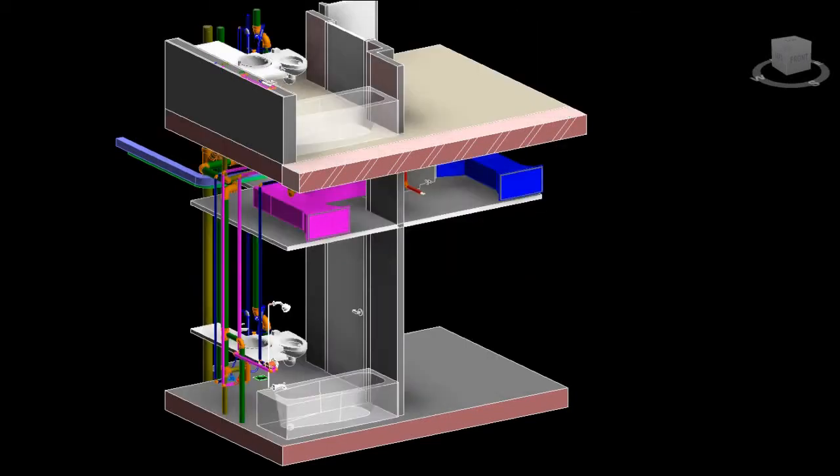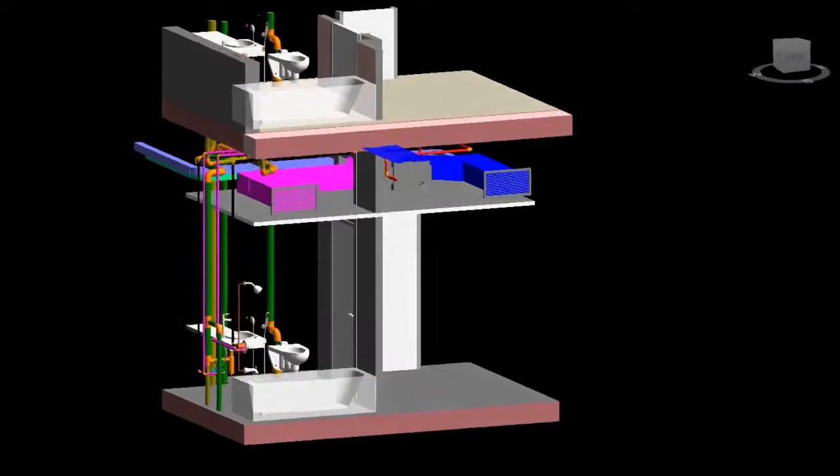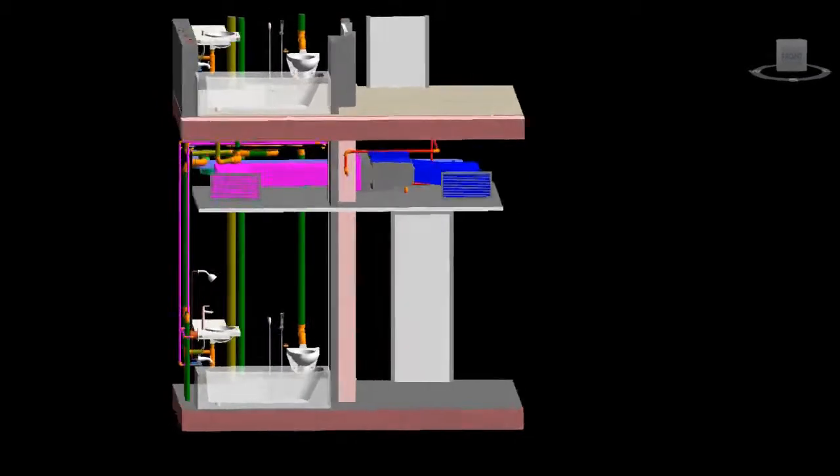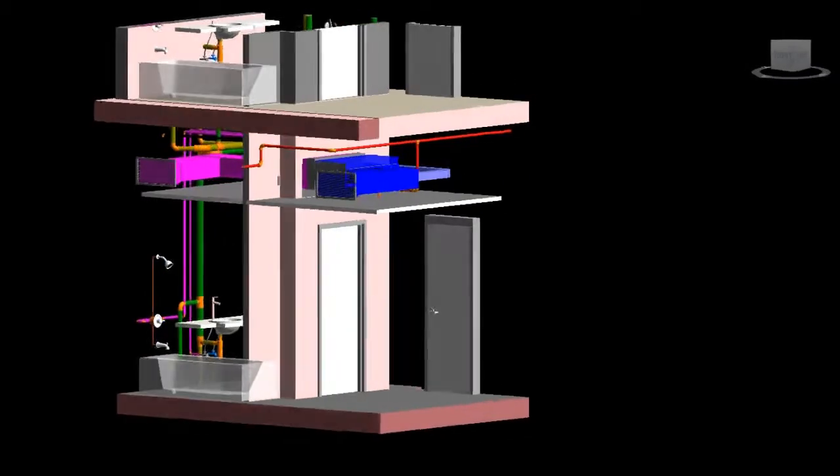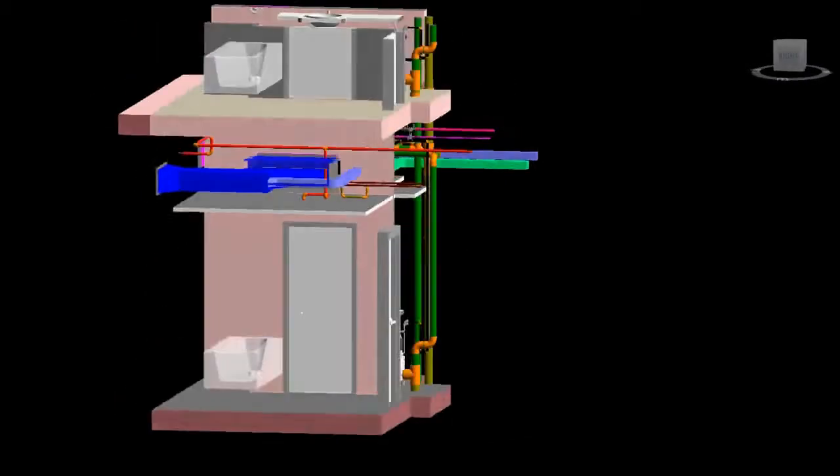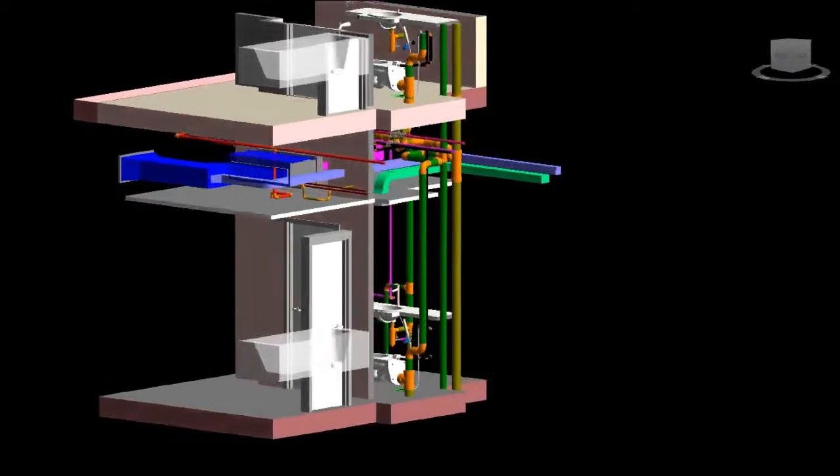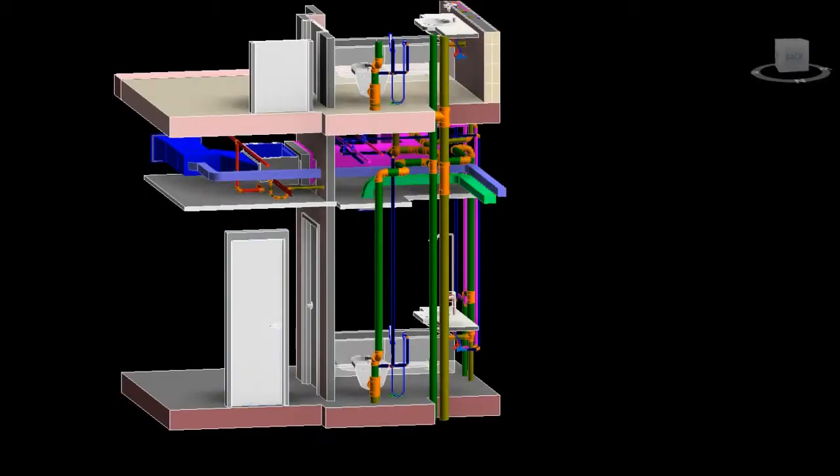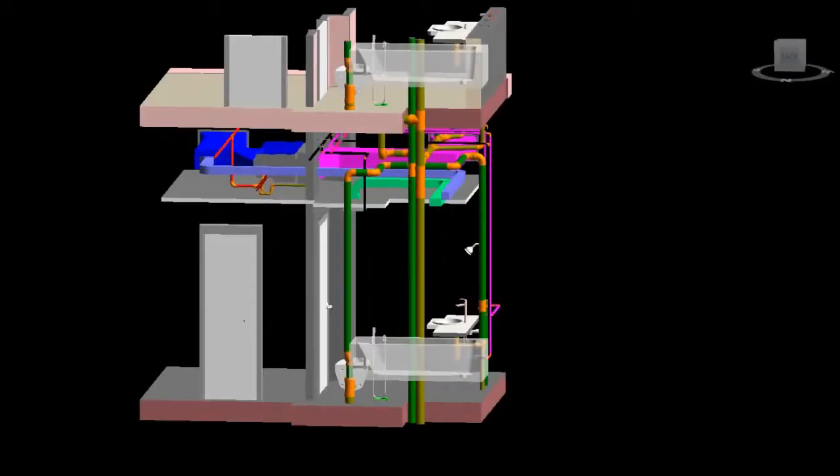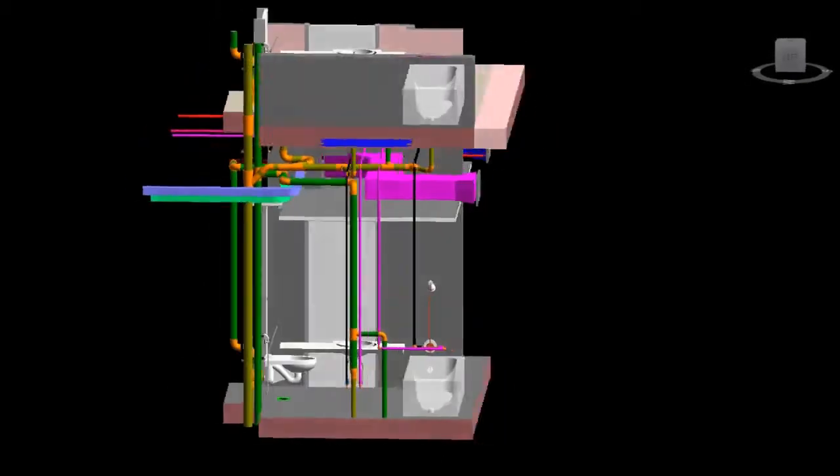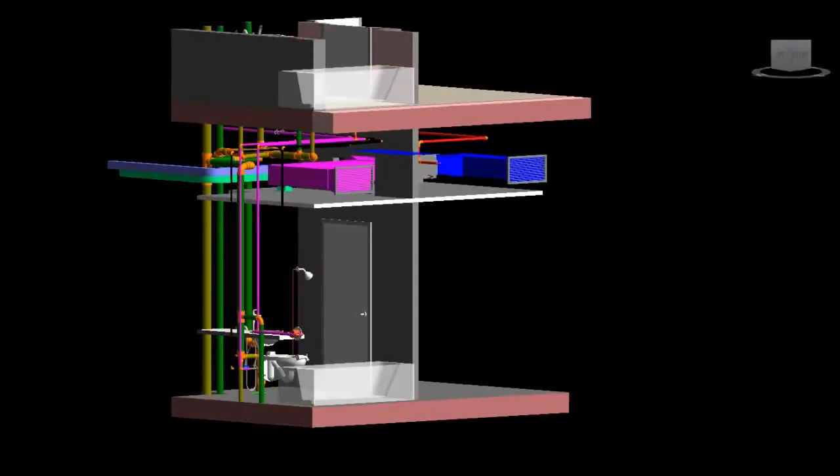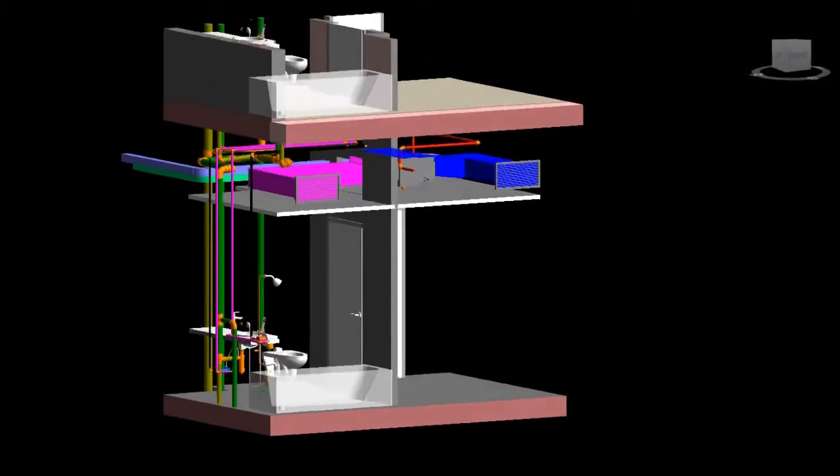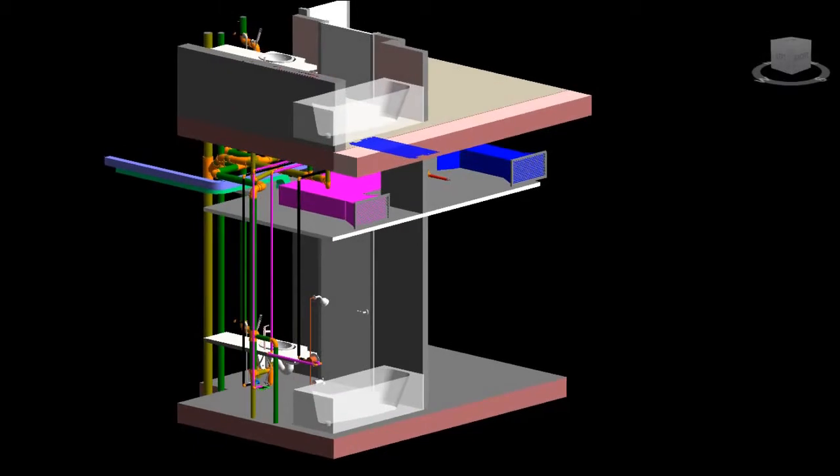Where 80% of the fan coil units were placed between the toilet walls. Hence the contractor was facing a problem to install the FCU's filter exactly between the toilet wall. Without a site inspection, BIM solves the problem perfectly.